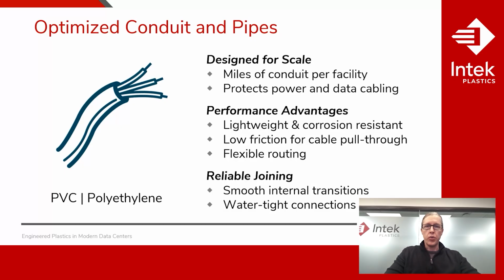Okay, optimized conduit and pipes. Conduit and piping systems extend throughout the data center, often totaling miles in length. Because of that scale, even small design details can have significant impact on installation time, long-term reliability, and maintenance. Plastics such as PVC and polyethylene are well suited for these systems due to their low weight, corrosion resistance, and ease of handling compared to metal alternatives. Their low coefficients of friction and high abrasion resistance support smooth cable pull through. This reduces installation effort and the risk of cable damage.